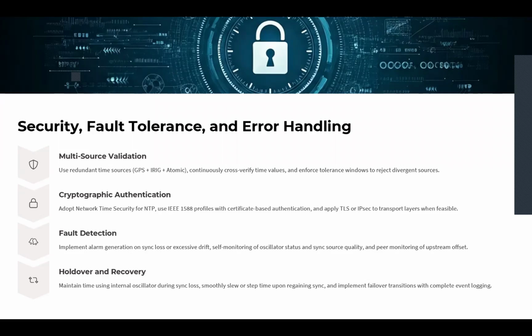When a fault is detected, we are mandated to generate a real-time alarm. These alarms must be designed to trigger operational modes like control loop isolation, degraded mode operation, or even system shutdown if safety is critical. If the system loses the master synchronization source, it must enter holdover. We already talked about that. In this mode, internal oscillators are used to free-run the clock. The performance of this holdover depends on the oscillator quality, temperature stability, and recent discipline history.